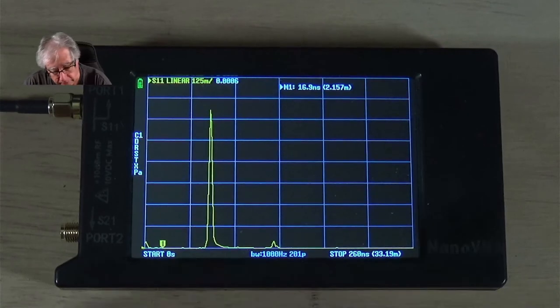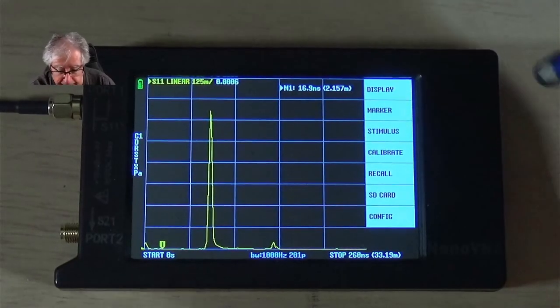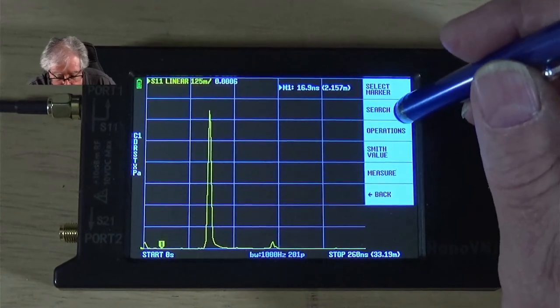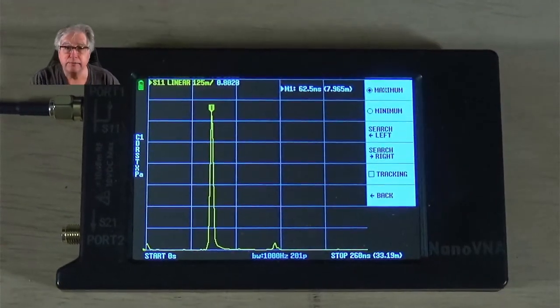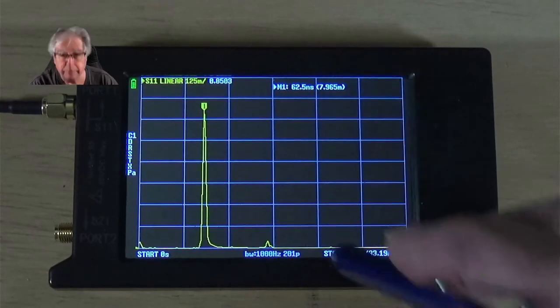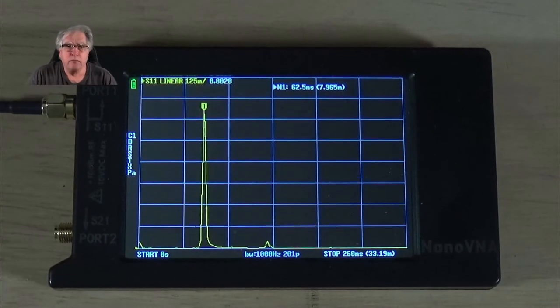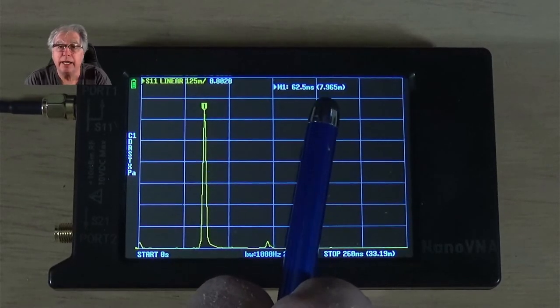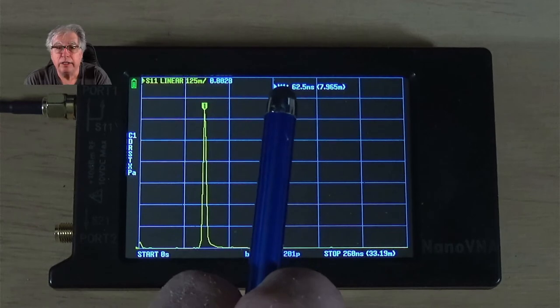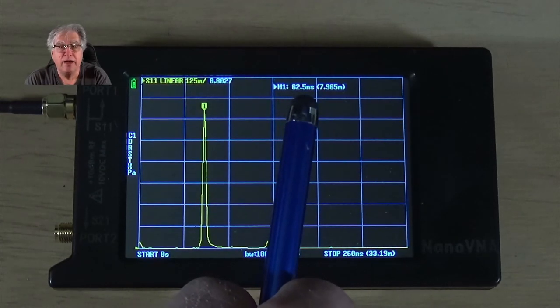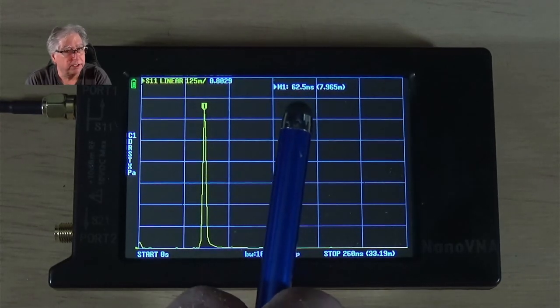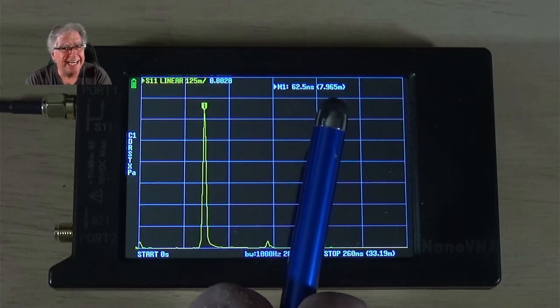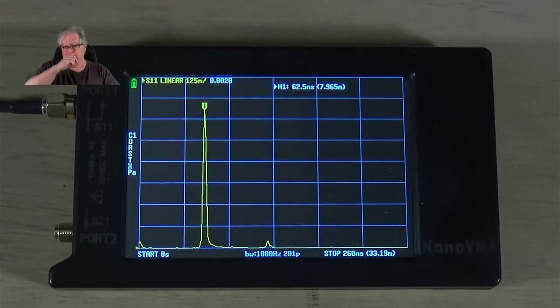So, I am going to jump to that, and I can do that by selecting marker, search, and just click on max. And, there I go, right to that. Now, I look at this, and it shows that my distance, okay, it took 62.5 nanoseconds for the reflection to take place. So, my distance is actually 7.965 meters.